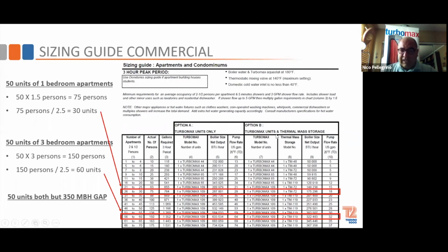You'll notice there's an A and a B. The A option is more for new construction or changing out the boiler. And B is you have a boiler that still has some life to it, but it doesn't have enough BTUs for that amount of water to be produced. You can add a buffer tank or a storage tank to the system, and now you have added BTUs from the thermal mass of that storage tank.